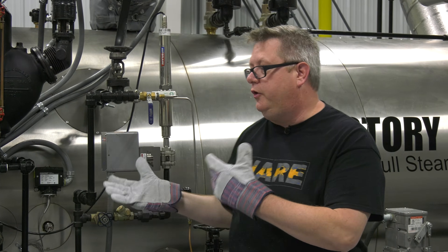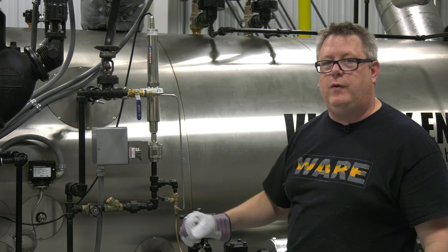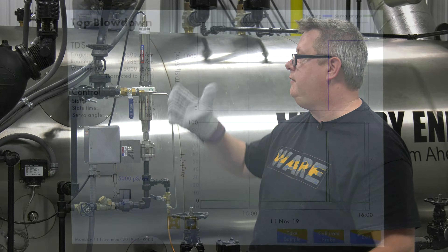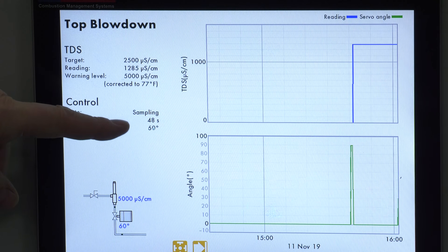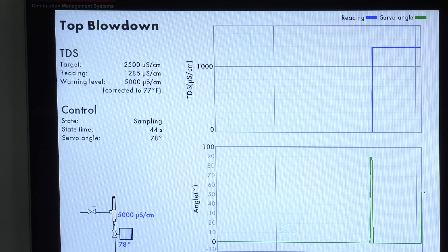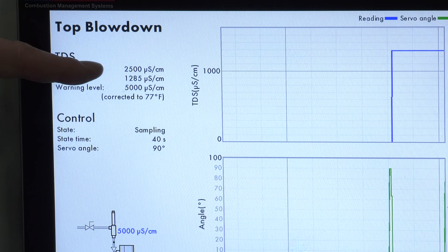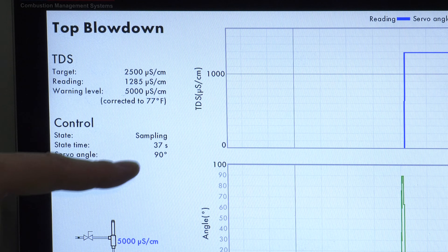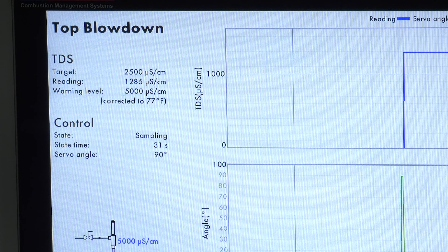Now in this case at BoilerU, we have an automated conductivity control system, so we can take a look on the control screen and see what we're doing there. Our automated system at specific intervals takes a sample of the conductivity — just like we would when we do chemical testing — and it determines whether we're at, below, or above set point and adjusts our servo angle accordingly. That takes a lot of the manual operation out of the surface skimming.